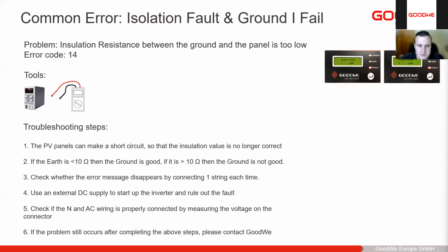You can check if the neutral and AC wiring is properly connected on the AC terminals of the device. We check the voltage between neutral and ground to make sure that there is less than 10 volts. If the problem still occurs after completing the steps, contact us for support.